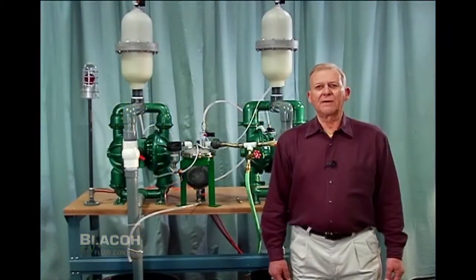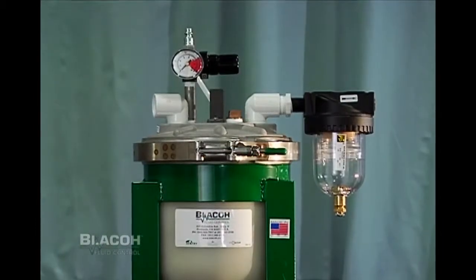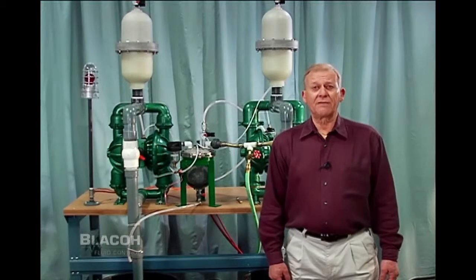The Biacoh Spill Stop is a very unique patented spill prevention device. It's a pneumatic device used primarily with air-operated double diaphragm pumps. It is designed to capture pump liquid when a pump's diaphragm fails so a spill won't occur.